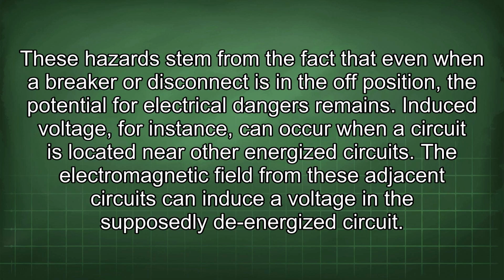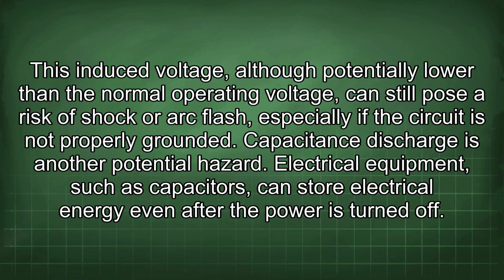These hazards stem from the fact that even when a breaker or disconnect is in the off position, the potential for electrical dangers remains. Induced voltage, for instance, can occur when a circuit is located near other energized circuits. The electromagnetic field from these adjacent circuits can induce a voltage in the supposedly de-energized circuit. This induced voltage, although potentially lower than the normal operating voltage, can still pose a risk of shock or arc flash, especially if the circuit is not properly grounded.